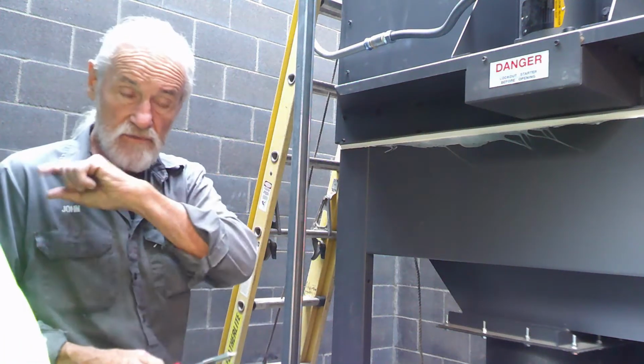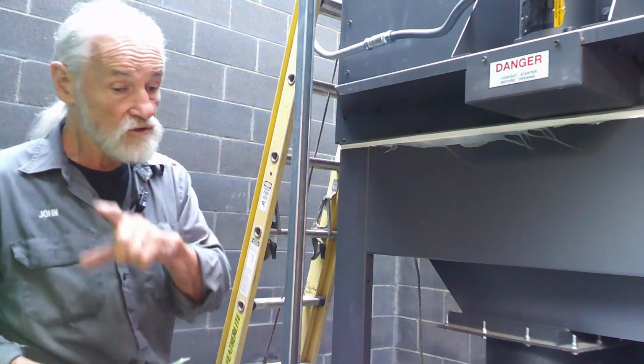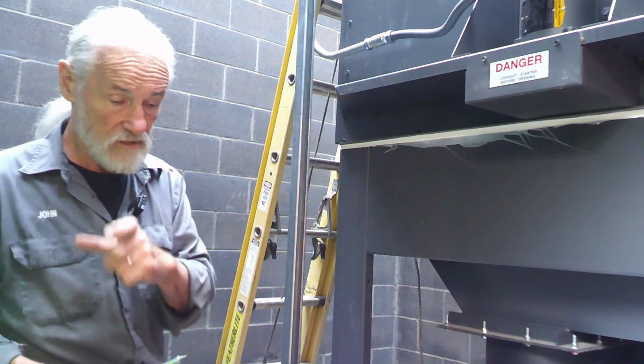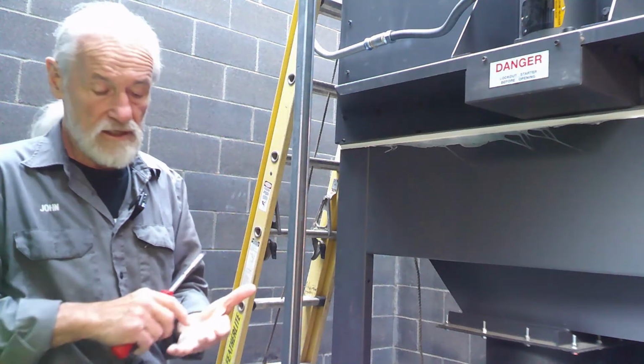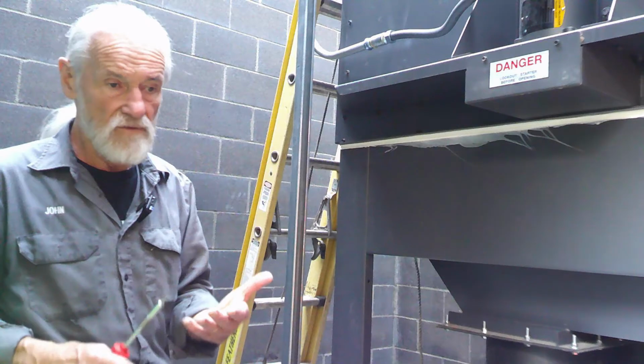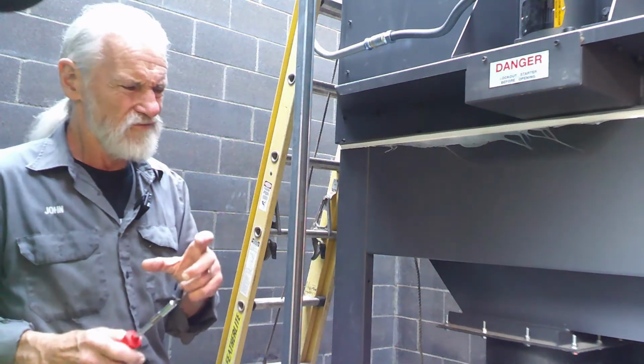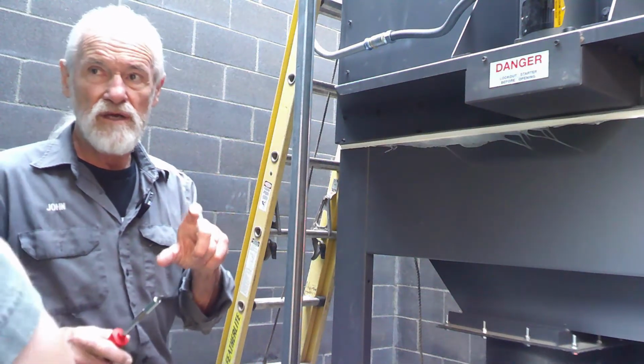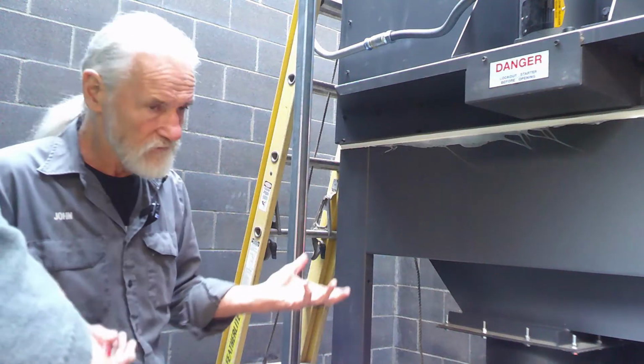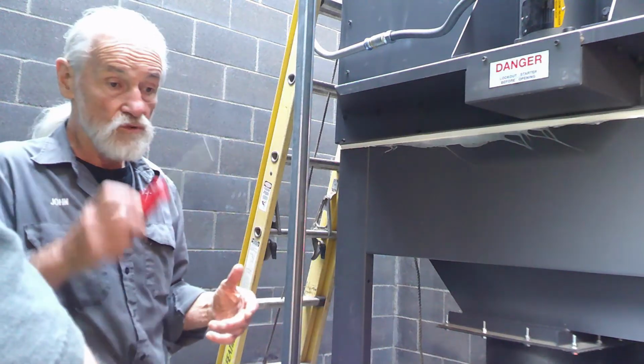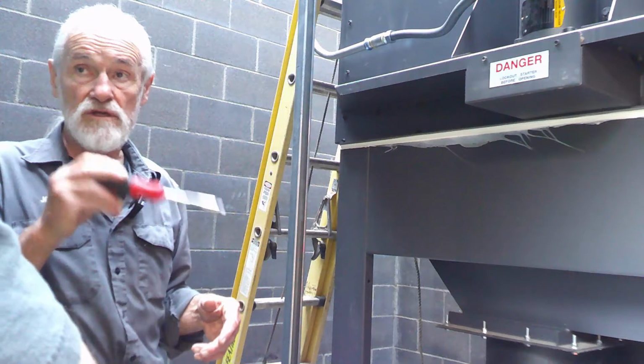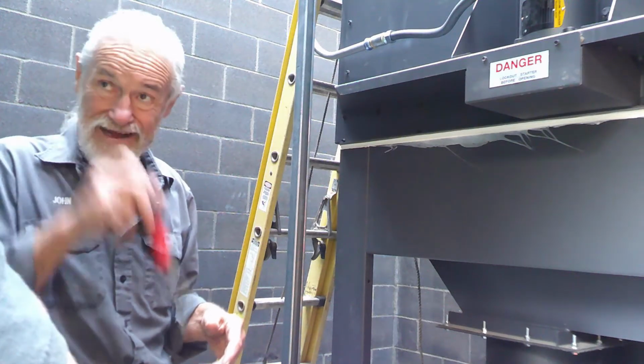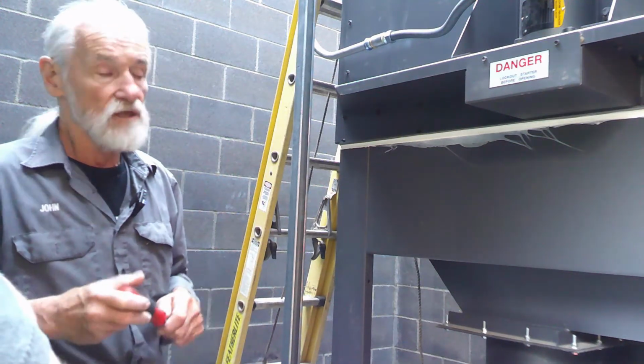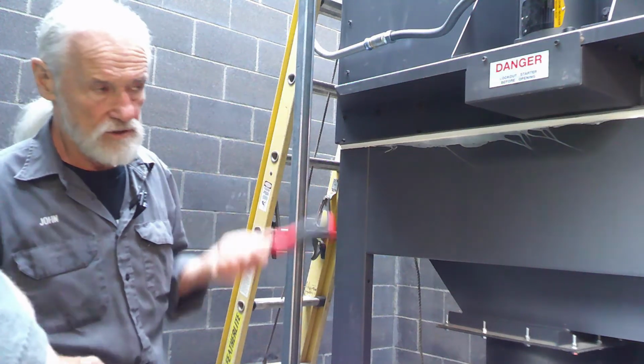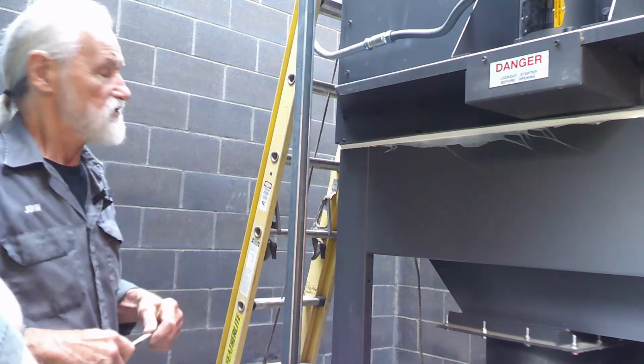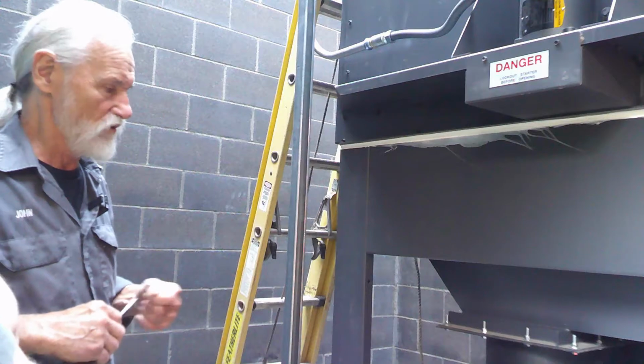Okay, so that can be done. There are 3 timers in there, and there's no literature connected to those timers. You have to go online, it's readily available, and it tells you. Those timers have 4 or 5 different functions. The wiring diagram, if we had it, shows you what it's set up as now, so you can see what it does and what it's supposed to be. That gives you a starting point, but if you're going to change it, you have to look it up. Unless you've done it many times, you're more likely to do it wrong.